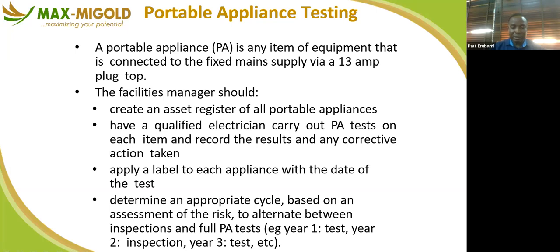And also set a process, create a process. Even if you are not there, you are out of that place tomorrow, anybody that is stepping into that office has records to work with. So in facility management, records are very, very important. It helps to do almost 70 or if not 80% of the job. It makes work easy for you. It will help you to set a routine maintenance. So you know when, oh, my generator is due for service, because you have the record. That's why on your generator, after maintenance, you put a record there, 250 hours for the next service, and so on. There are some you do every year, every 3 years, and so on.